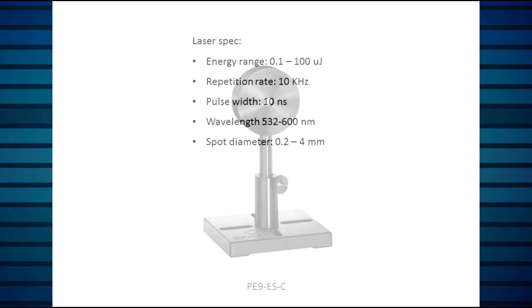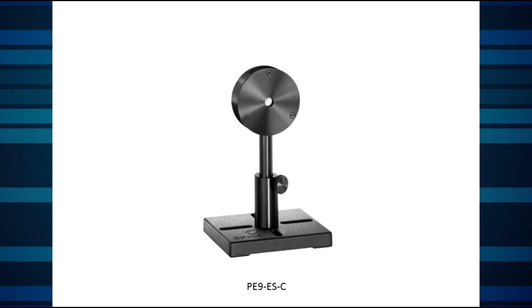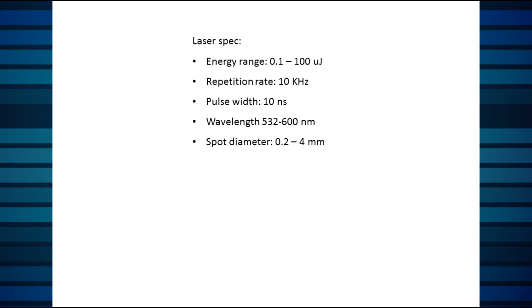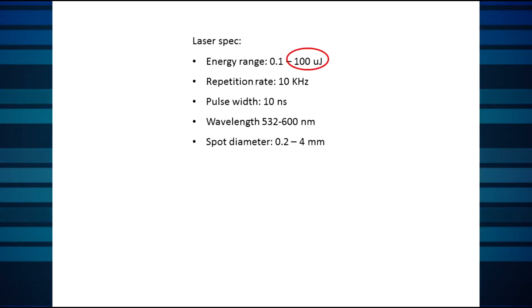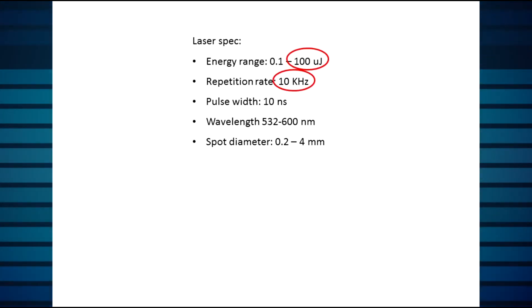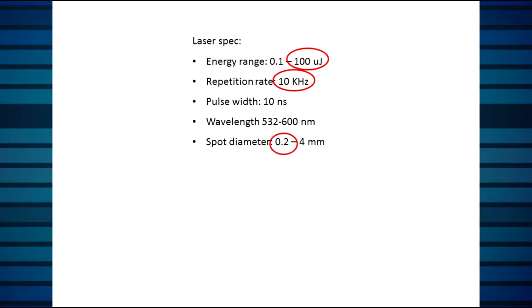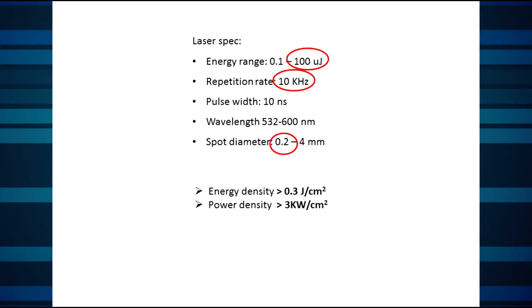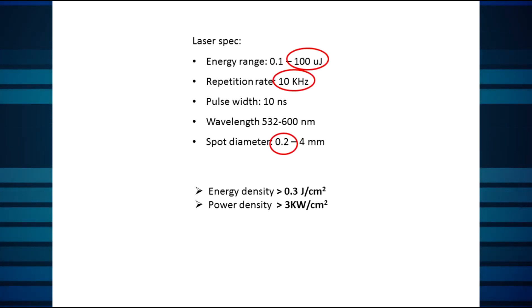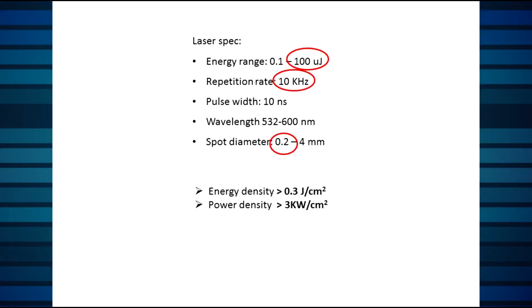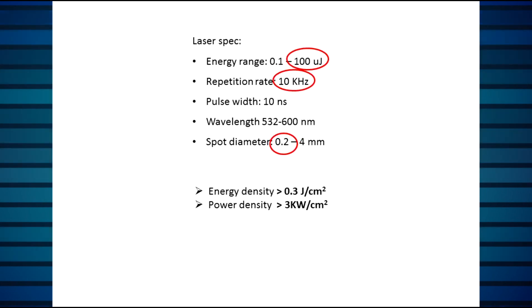For this energy range, we have an energy sensor called the PE9-ES-C. But hang on — combining the worst-case numbers: energy 100 microjoules, pulse rate 10 kHz, and 0.2 mm spot diameter, we find an energy density somewhat over 300 mJ per square centimeter. That's reasonable. But power density is over 3 kW per square centimeter, which will clearly have to be reduced.